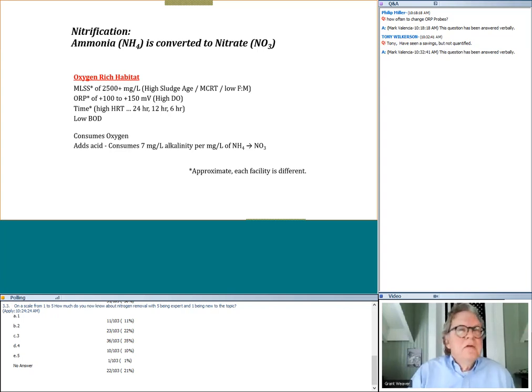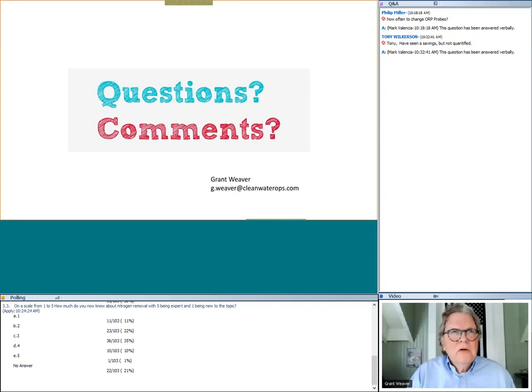Here in the Northeast, I'm speaking to you from Connecticut. We have granite soils, very low alkalinity in our water, and many facilities struggle to have the pH, the alkalinity available to support ammonia removal, and actually have to add a base, some kind of a sodium hydroxide, caustic soda, or something a little less human toxic than that, nasty burn type materials. Any questions on ammonia removal before we get to the next step?